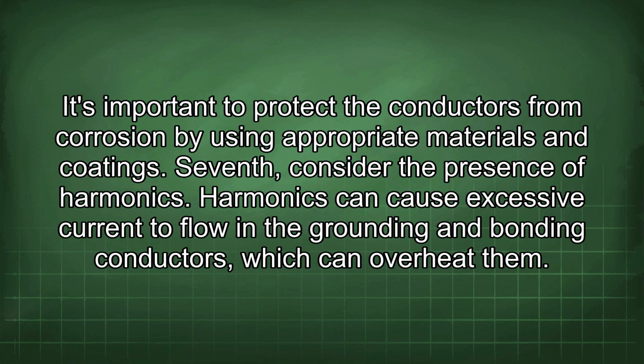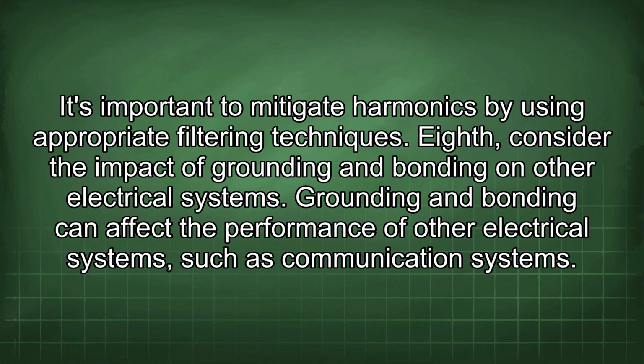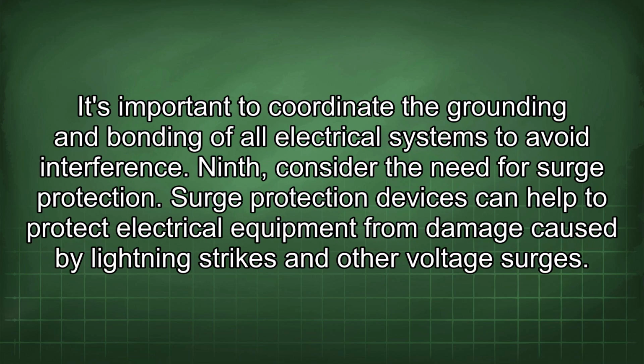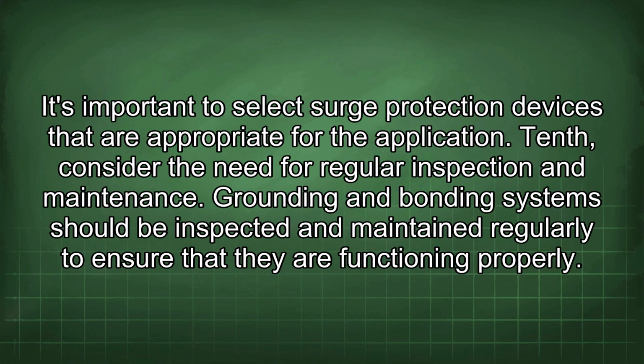Seventh, consider the presence of harmonics. Harmonics can cause excessive current to flow in the grounding and bonding conductors, which can overheat them. It's important to mitigate harmonics by using appropriate filtering techniques. Eighth, consider the impact of grounding and bonding on other electrical systems. Grounding and bonding can affect the performance of other electrical systems, such as communication systems. It's important to coordinate the grounding and bonding of all electrical systems to avoid interference. Ninth, consider the need for surge protection. Surge protection devices can help to protect electrical equipment from damage caused by lightning strikes and other voltage surges. It's important to select surge protection devices that are appropriate for the application.